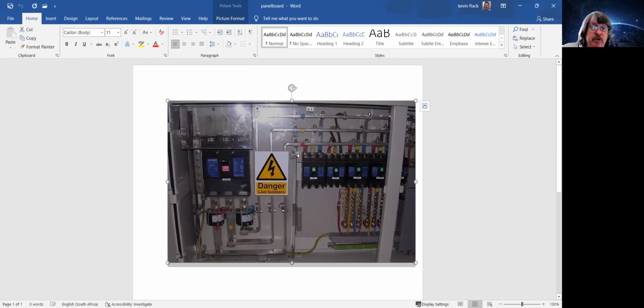We can also see with this sort of approach here is that there's absolutely zero compartmentalizing. So even if this product, as the main, had a huge flash on the top, it would probably continue right into this zone as well and destroy the whole panel. Or a breaker tripping on the load side here and causing a flash in the top. There's going to be dynamic stresses with interface forces here, and the arc could be forced to travel up or down this bus bar until it reaches the end and flashes over to ground.